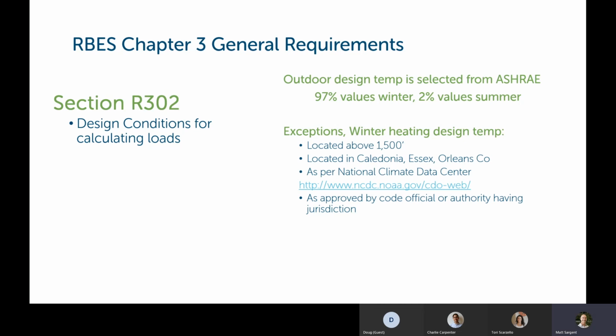And more general requirements. Section R302 is about calculating design conditions for calculating loads. So we're using ASHRAE 97% winter values and 2% summer values. Here are the exceptions that I mentioned earlier. Winter heating design temp, if you're located above 1500 feet, you can use a different design temp. If you're located in Caledonia, Essex, or Orleans counties, you can use a different winter heating design temp.